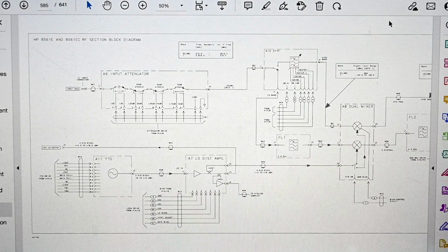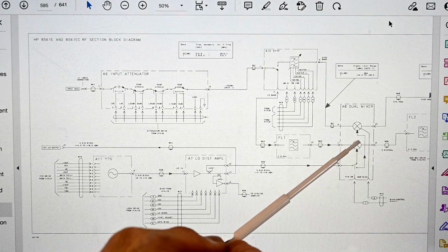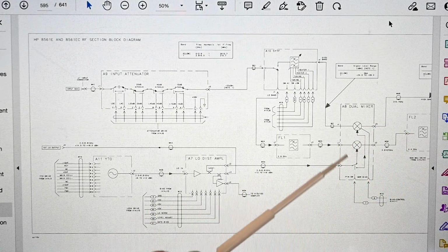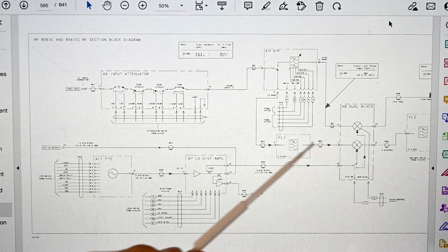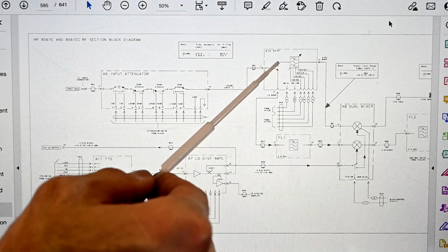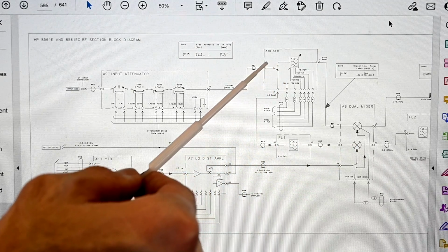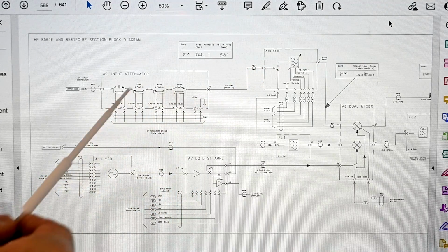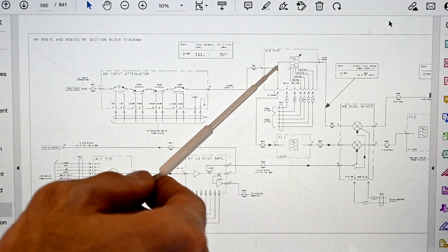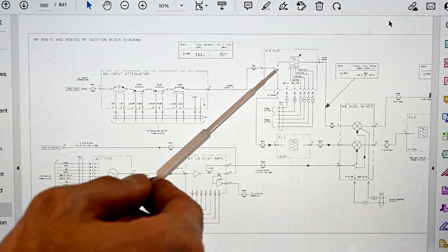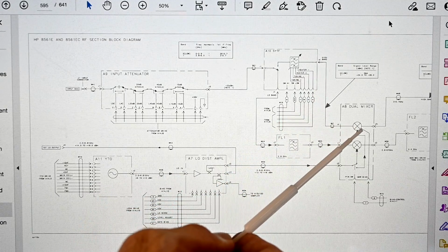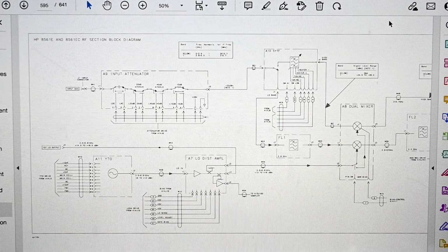Now it mentioned that if the test that we just did looked okay, the problem was probably not after this mixer, and that eliminates a lot of components. So it looks like the problem is prior to that, and if it's just going through this switch, then the next step prior to that, because I believe that switch is working okay, is this attenuator assembly. Now if this switch goes up to the high band, then it goes through the Yig-tuned filter and then passes over here and then over to the A8 dual mixer.